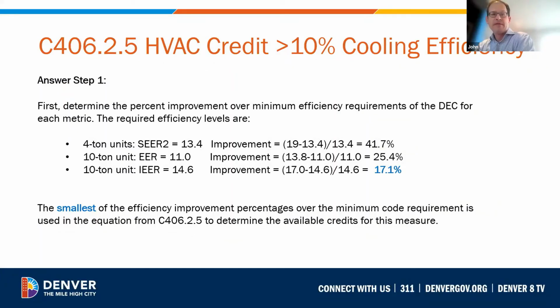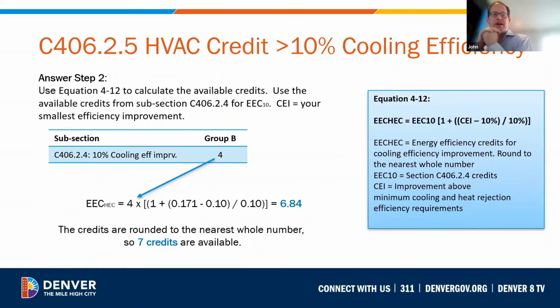And for this case, the limiting factor is the IEER. The efficiency rating would have just a 17% improvement. So you would be able to claim at least 10% improvement beyond the minimum efficiency levels for that credit point. So once again, the credits would be calculated using the available credits and rounding up to the whole number. So since we can round up beyond the 10%, if 10% gives us 4 credits from the credit tables in the code, we would be able to round up and get 7 credits by getting a 17% reduction instead of 10% reduction. So this is a way to incentivize very high performance equipment on projects that may be used.